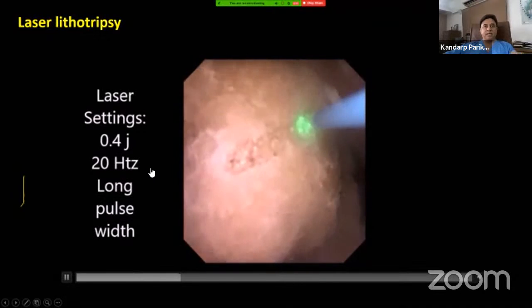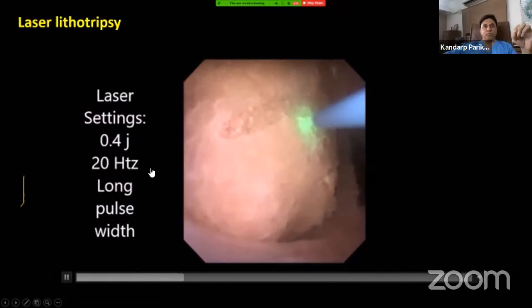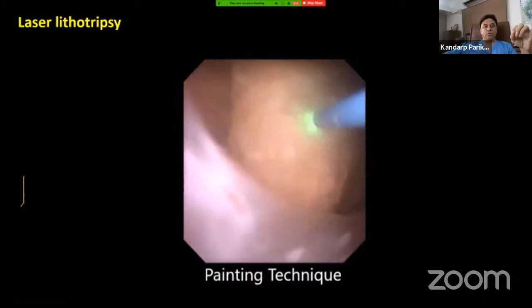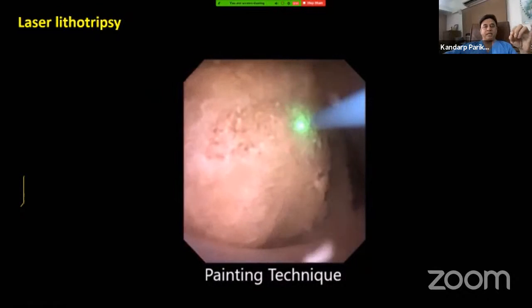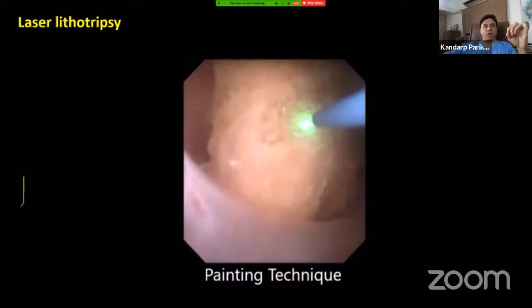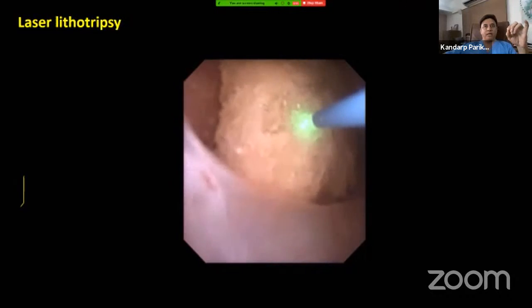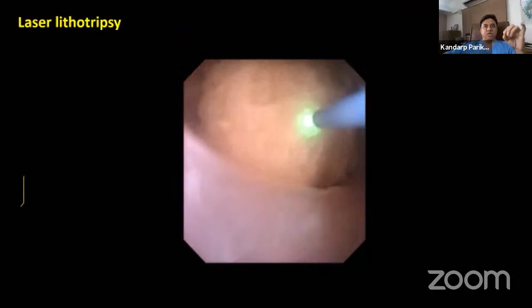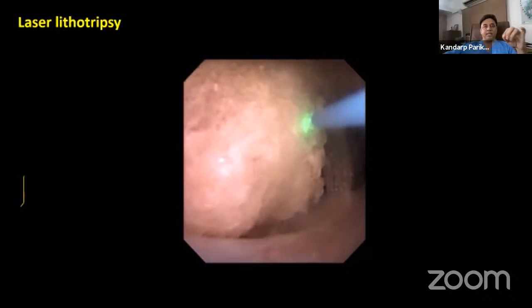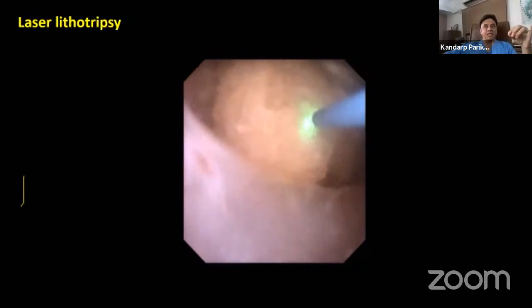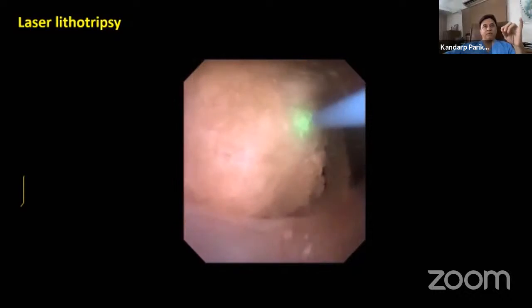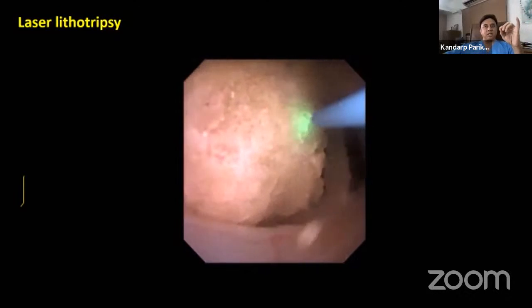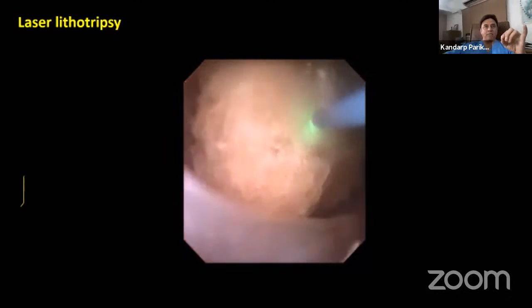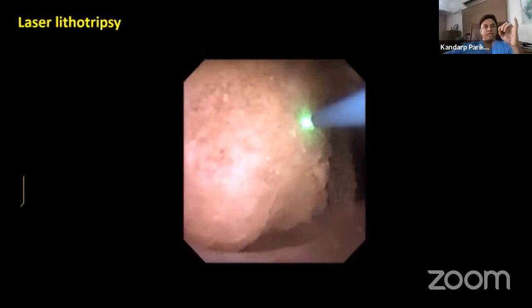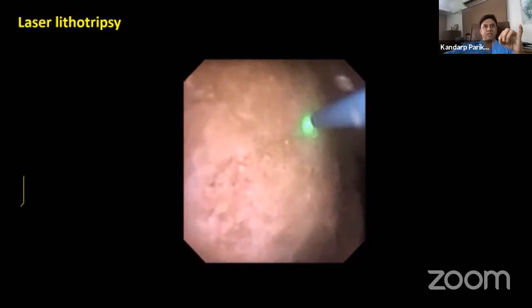Here, for the energy setting, when I want to produce dusting, I use a painting technique with a laser setting of 0.4 joule and a frequency of 12 to 15. Then gradually, if you have a high power laser, you can increase the frequency. The frequency will increase the speed of the procedure. That will not help the dusting. It will increase the speed of the procedure.